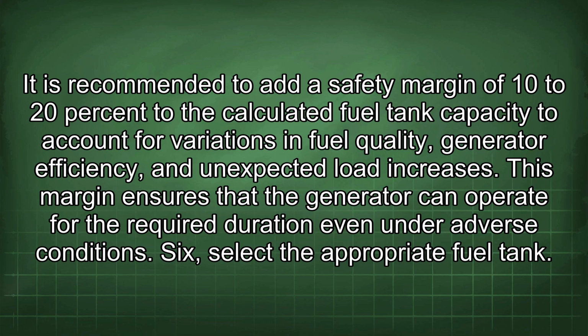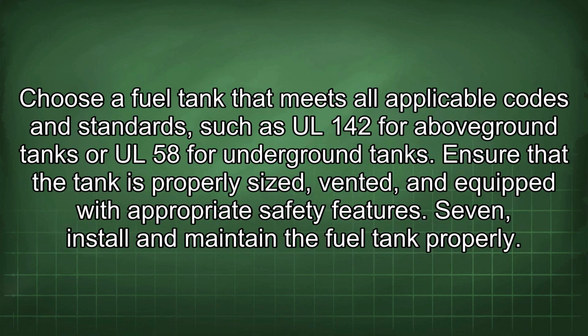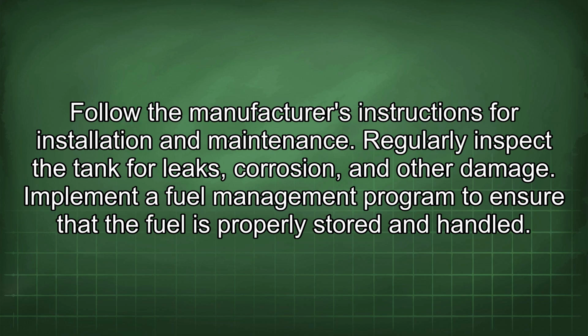6. Select the appropriate fuel tank. Choose a fuel tank that meets all applicable codes and standards, such as UL 142 for above-ground tanks or UL 58 for underground tanks. Ensure that the tank is properly sized, vented, and equipped with appropriate safety features. 7. Install and maintain the fuel tank properly. Follow the manufacturer's instructions for installation and maintenance. Regularly inspect the tank for leaks, corrosion, and other damage. Implement a fuel management program to ensure that the fuel is properly stored and handled.